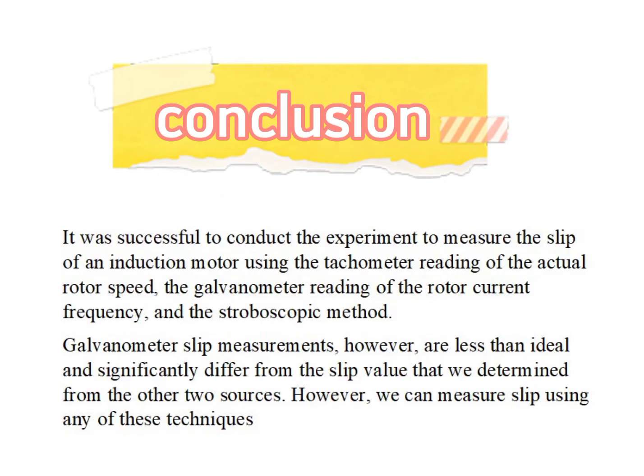From this practical, we can conclude that the measurement of slip can be done using the tachometer reading of actual rotor speed, the galvanometer reading of the rotor current frequency, and the stroboscopic method. The values of slip for all these methods were close to each other except for the galvanometer whose value deviated further from the other two. However, this practical validated the use of any three of these techniques to measure the slip of an induction motor.